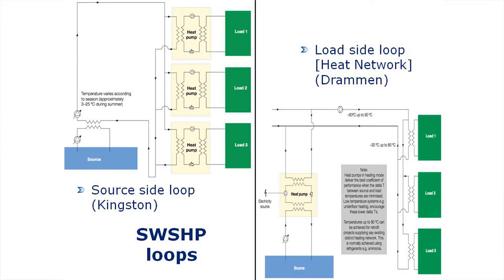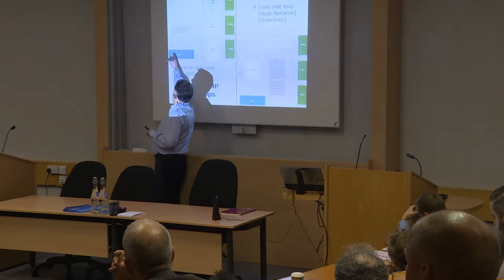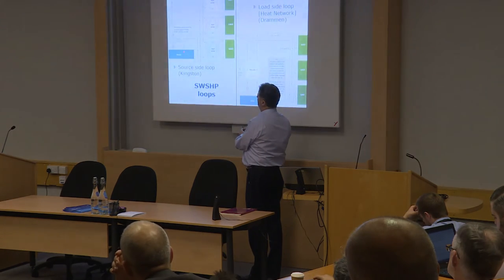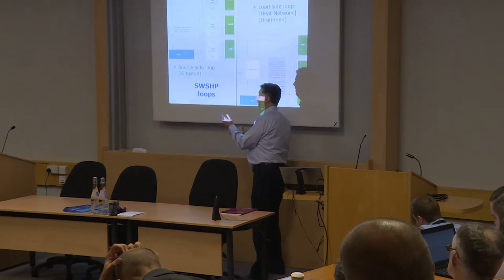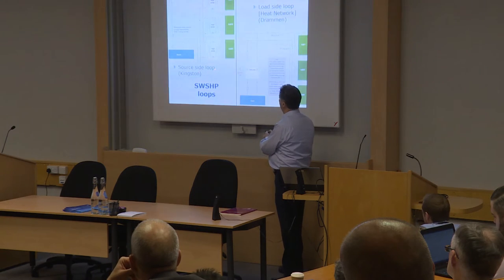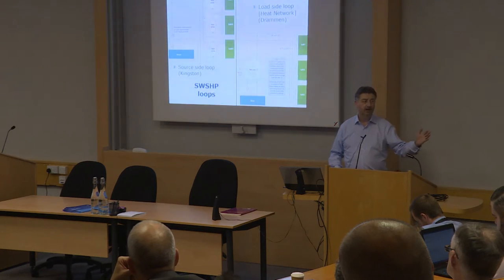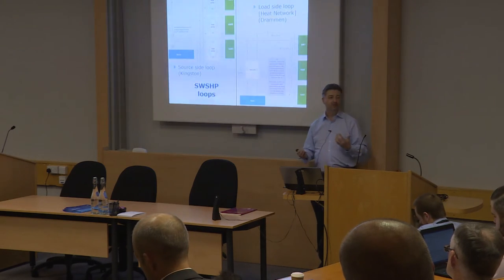But the other sort of loop we've come across is the approach in Kingston Heights, which is an ambient loop - not ambient air, but ambient at river temperature. This loop abstracts here through a plate heat exchanger, forming an ambient loop between 3 and 25 degrees, though we're finding it's between about 10 and 25 for quite a lot of the year. It supplies lots of little 10 kilowatt heat pumps around the building, some heating and some cooling, giving a heat exchange between them. That's a very interesting approach, I think.